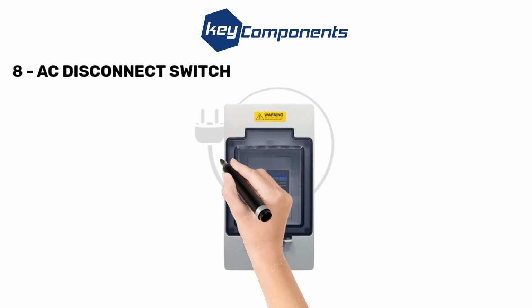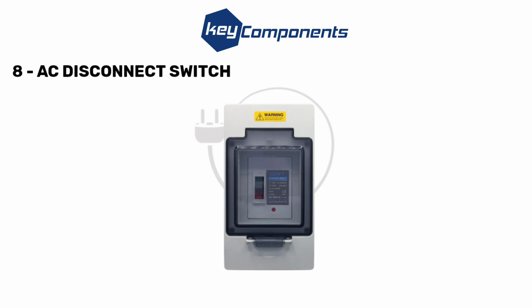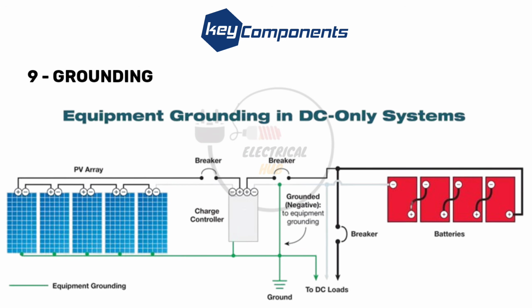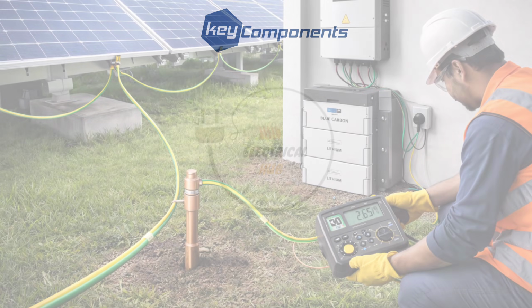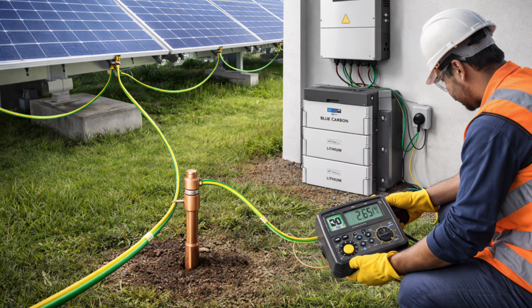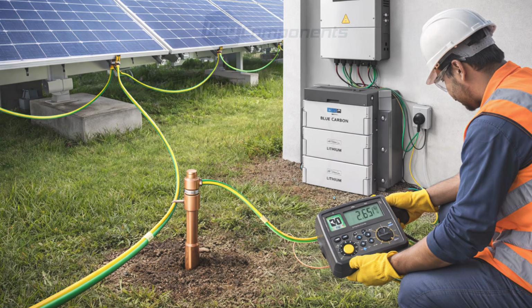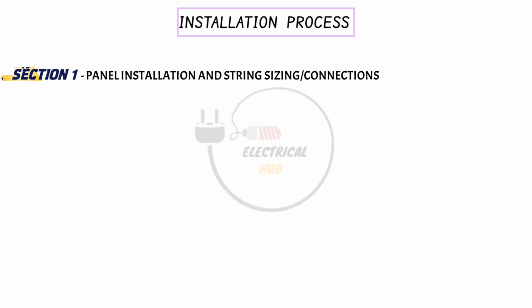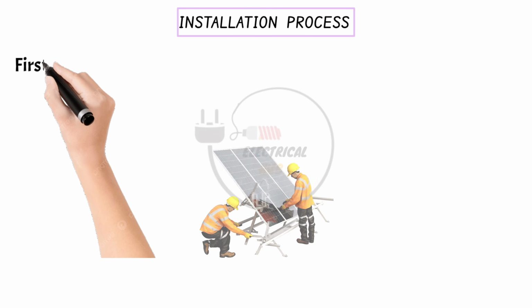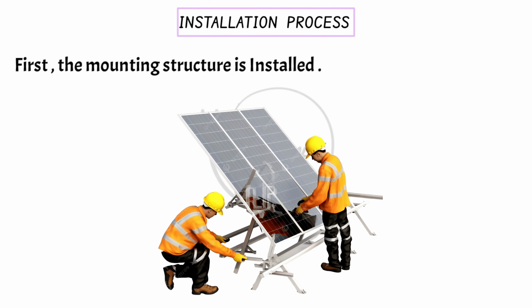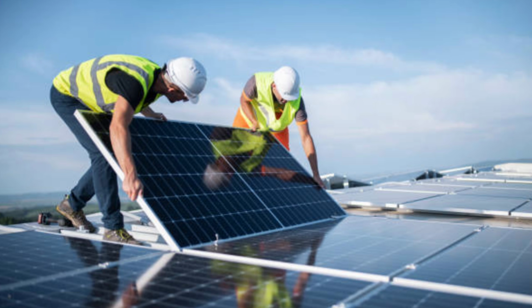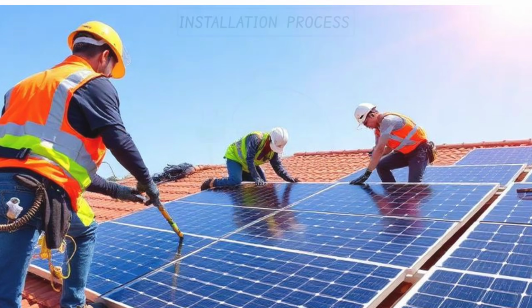8. AC disconnect breakers. They protect installers, maintenance personnel and homeowners from electrical shock when they work on the solar system. 9. Grounding. Grounding is a critical safety feature for any solar power system. AC and DC grounding along with bonding protect against electrical hazards and ensure the system's safe and reliable operation. Now let's get into the installation process. Section 1. Panel installation and string sizing connections. First, the mounting structure is installed, ensuring it's securely attached and aligned correctly. The solar panels are mounted on the structure.